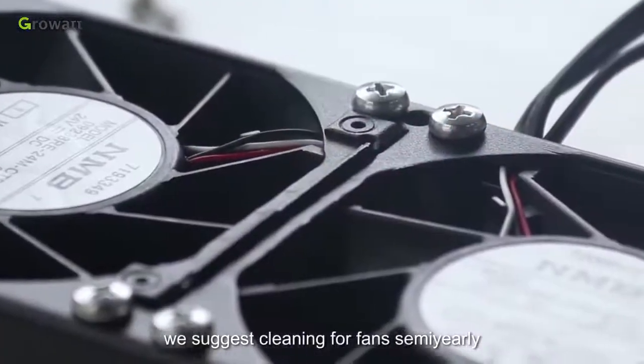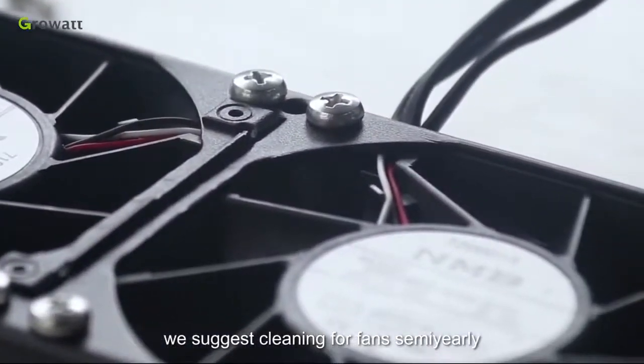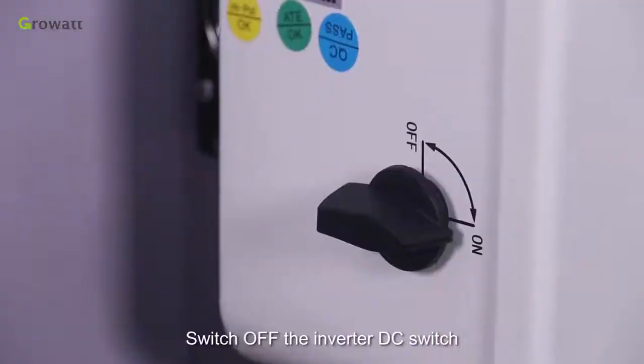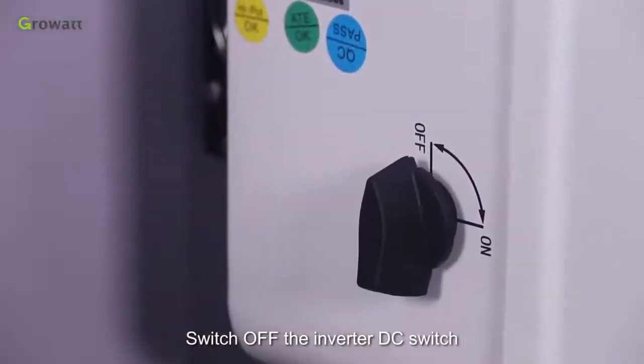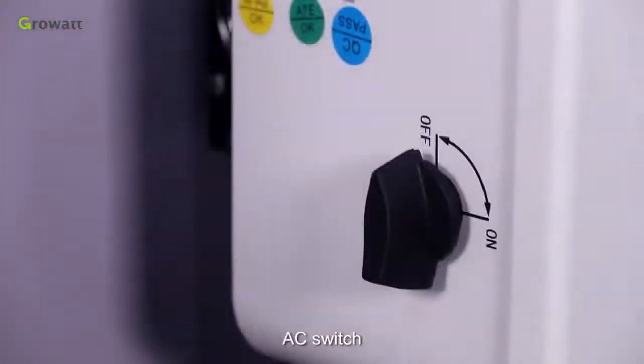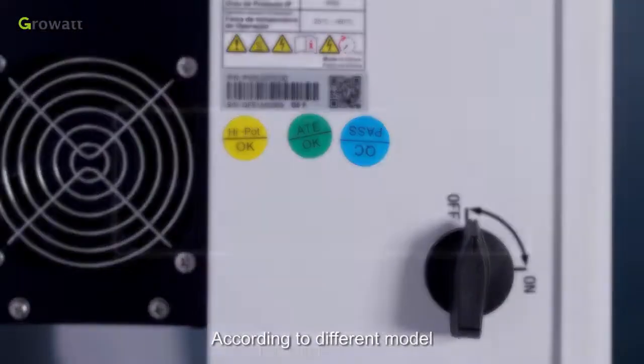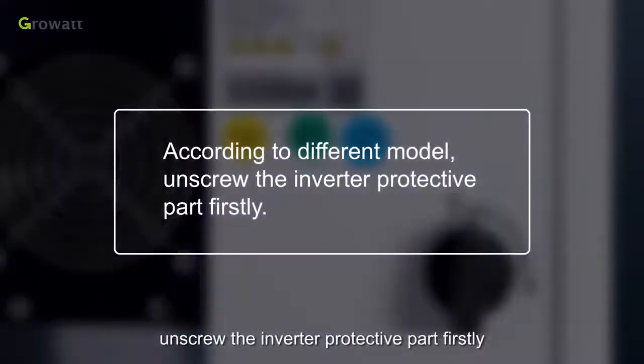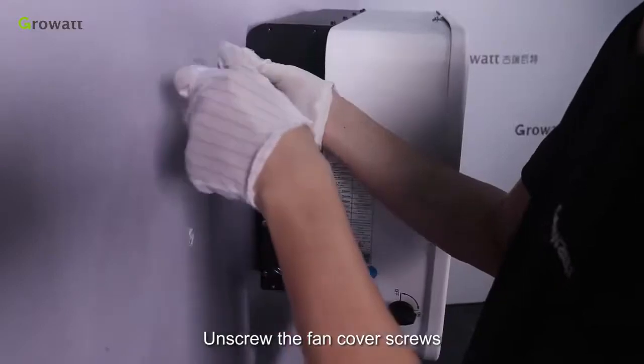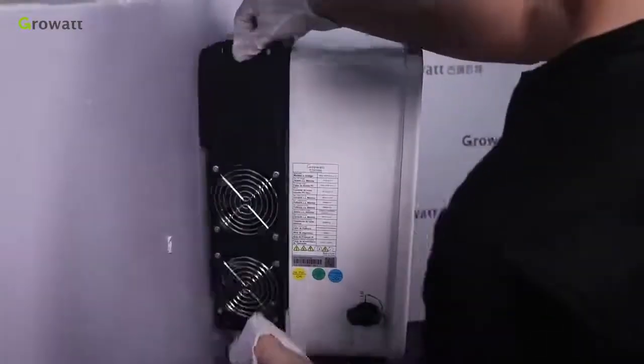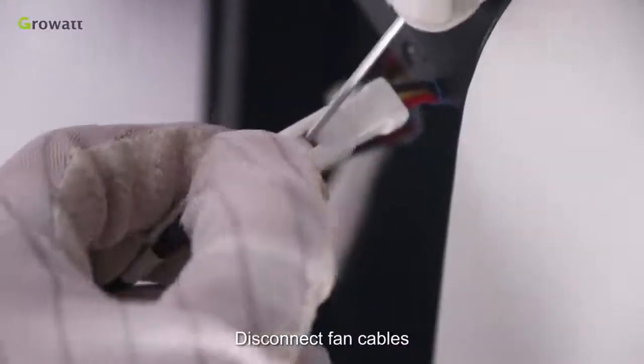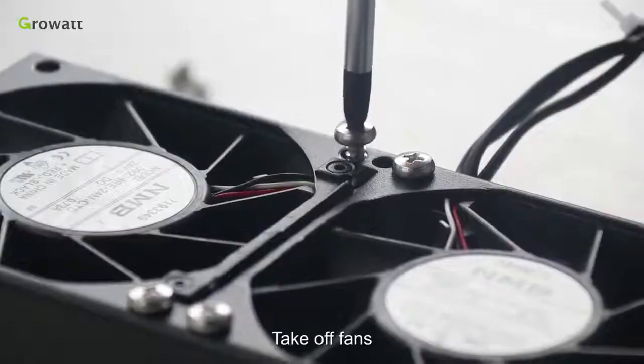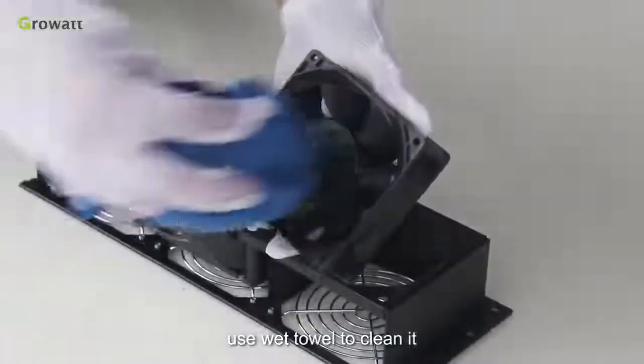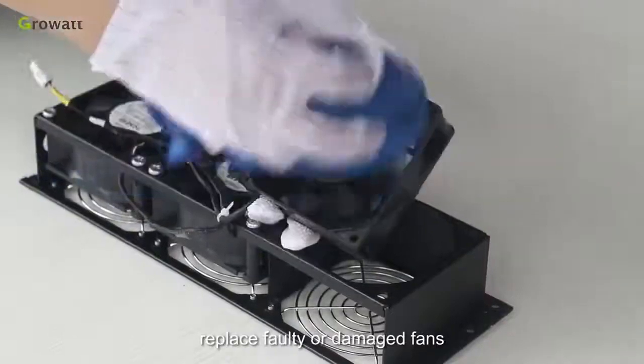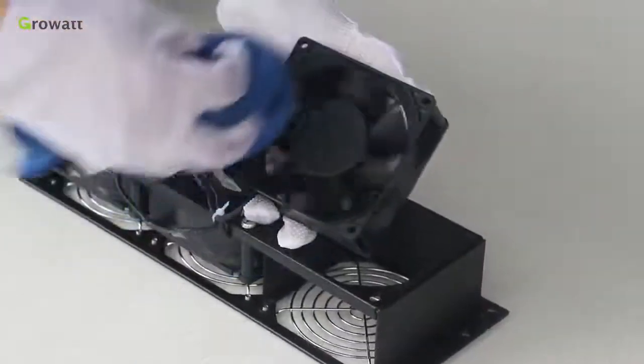For outdoor installations, we suggest cleaning the fans semi-yearly. Switch off the inverter DC switch and AC switch. According to different models, unscrew the inverter protective part first. Unscrew the fan cover screws. Disconnect the fan cables. Take off the fans. Use a wet towel to clean them. Replace faulty or damaged fans.